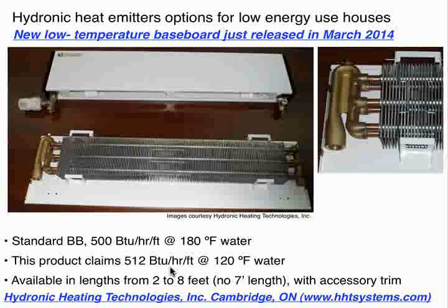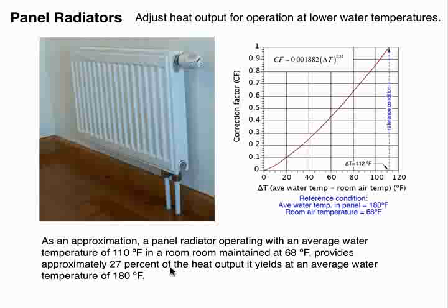Again, a couple quick examples of some fin tube that's available. Panel radiators can be designed around these low water temperatures, but the key thing is you have to correct the output data.